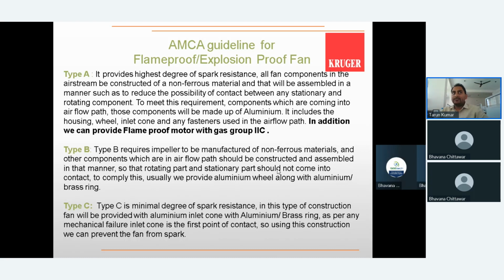In multiple cases, we are seeing that at the same time BOQ called for the spark resistance type, it will also ask for the smoke exhaust. So I just want to clear it out. A smoke fan cannot be used for spark ventilation, and a spark resistant fan cannot be used for smoke ventilation, because both the motor features are different.